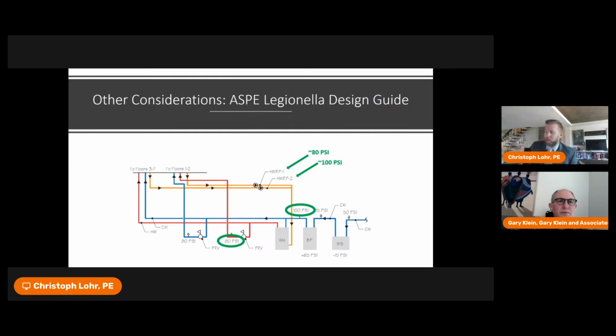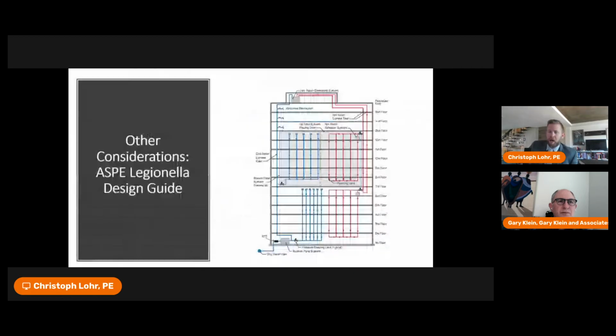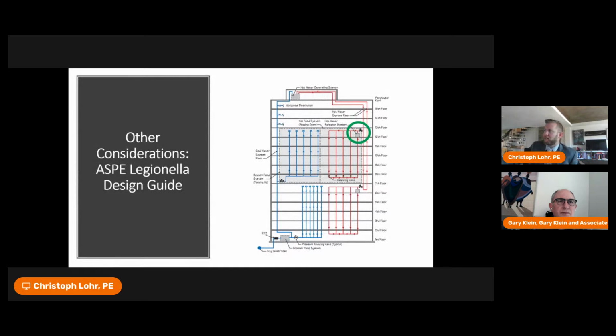You need a reheat heater, which is a concept we see in high-rise design, where you have an express riser from your hot water generation system, and you loop downstream of the pressure reducing valve, and you have a reheat heater and recirculation pump in that system to account for the heat losses in that zone from multiple floors.